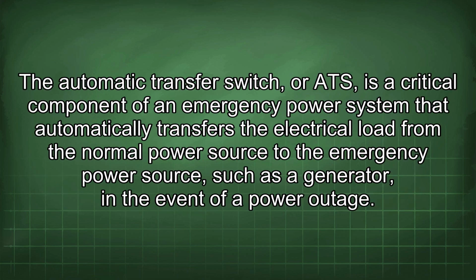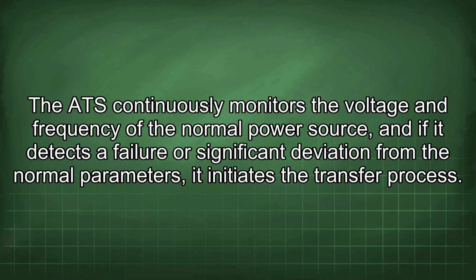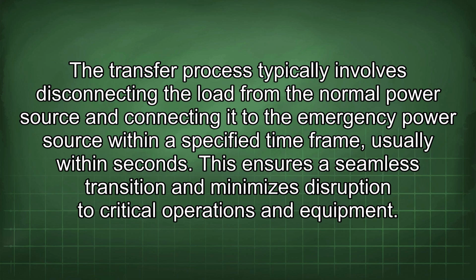The automatic transfer switch, or ATS, is a critical component of an emergency power system that automatically transfers the electrical load from the normal power source to the emergency power source, such as a generator, in the event of a power outage. The ATS continuously monitors the voltage and frequency of the normal power source, and if it detects a failure or significant deviation from the normal parameters, it initiates the transfer process. The transfer process typically involves disconnecting the load from the normal power source and connecting it to the emergency power source within a specified time frame, usually within seconds. This ensures a seamless transition and minimizes disruption to critical operations and equipment.